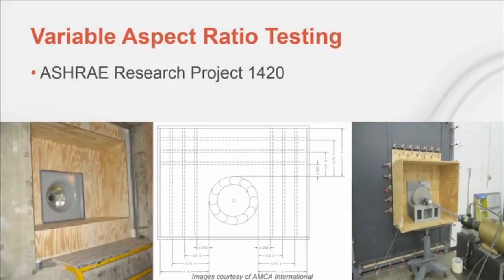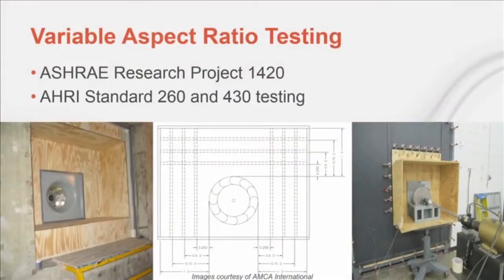The good news is that much work has been done in this area to better understand how the cabinet affects fan performance. ASHRAE-sponsored and in-house manufacturer testing has narrowed this gap of understanding. The results of ASHRAE Research Project 1420 were presented in 2015. This project explored a number of system effects related to plenum fans and in particular focused on uniform cabinet sizing relative to the fan. Some manufacturers have taken this a step further and tested a variety of air handler configurations to fill many of the gaps in the ASHRAE research.